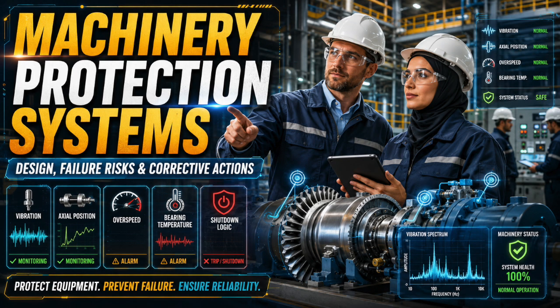This is where measurement discipline matters. A poor casing vibration installation can make a healthy machine look bad. A poor filter selection can make noise look like danger. A weak mounting point can turn structural resonance into false alarm. So again, the question is not only what does the vibration value show? The question is, does this value represent the failure mode I care about?